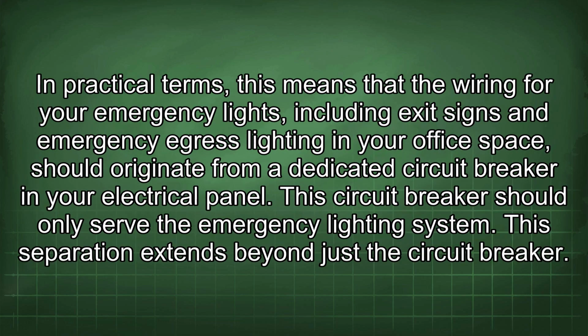In practical terms, this means that the wiring for your emergency lights, including exit signs and emergency egress lighting in your office space, should originate from a dedicated circuit breaker in your electrical panel. This circuit breaker should only serve the emergency lighting system. This separation extends beyond just the circuit breaker.